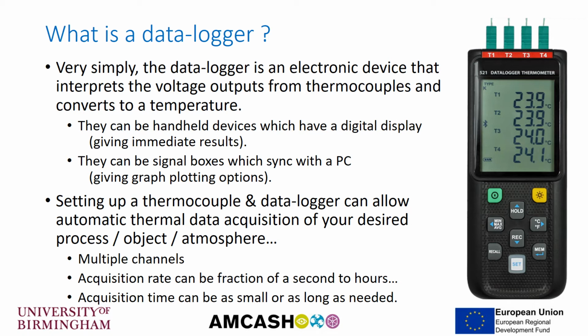We can set up our thermocouple and our data logger to allow for automatic thermal data acquisition of your desired process or object or atmosphere. A data logger will have multiple channels. We can change the acquisition rate from maybe a fraction of a second to hours. We can change our acquisition time from as small as you want to as long as you need.